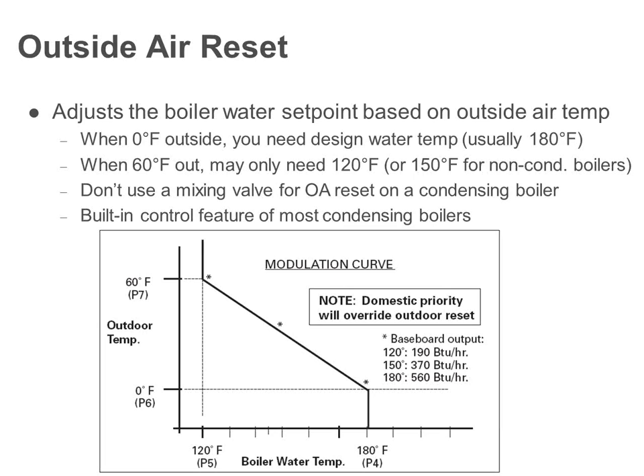So one thing that people will get a little freaked out about is they'll say, hey, my boiler's running all the time. You ask them, hey, let me show you something. Look inside this little sight glass here. And you see how small that flame is? It looks like a bunch of little match tips. Instead of being 100,000 BTUs like your old boiler, it's just kicked on and off and banged 100,000 BTUs on. This thing's sitting here and it only needs 20,000 BTUs an hour to heat your house. So that's what outdoor air reset does. It basically helps us modulate as low as possible. So like Ryan showed you on those other graphs, it raises the efficiency as much as possible.